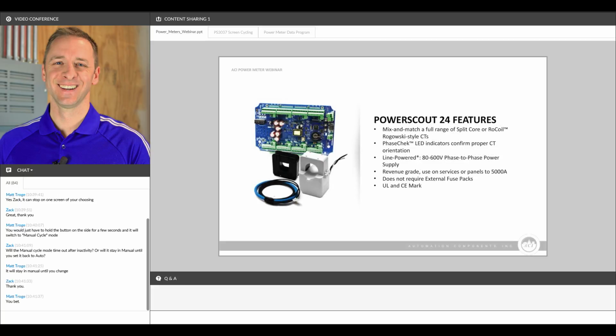It uses the same types of CTs, whether the split core or the Rogowski style rope CTs, and it also has the same phase check LED indication system that shows you whether the CTs are oriented and installed properly, so that speeds up installation and reduces errors. And it's powered by the load being monitored up to 600 volts, and again, it doesn't require any external fuse packs. And it does carry both the UL and the CE listing.